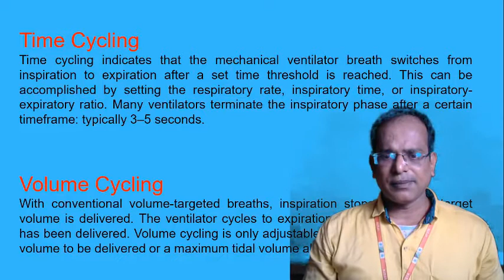Next we will discuss volume cycling. With conventional volume targeted breaths, inspiration stops once the target volume is delivered. The ventilator cycles to expiration once the tidal volume has been delivered. Volume cycling is only adjustable in that the clinician sets a tidal volume to be delivered, or a maximum tidal volume alarm is set.